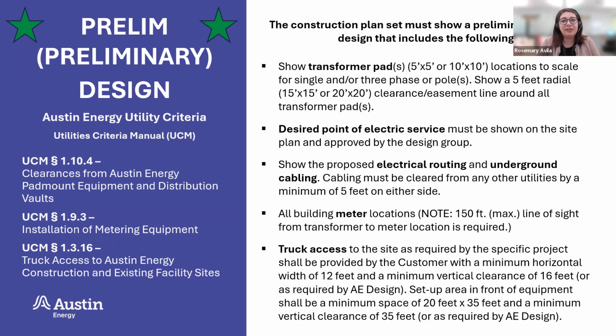You need to install a new pole. You need to connect to a different pole. So that's why we want it shown early on so we can start making those determinations. We want every proposed electrical routing underground shown. And again, that's to measure clearances, make sure you're not going under a pond or under a building or under a huge retaining wall or something like that. So we do need the routing shown and make sure that we maintain distances from that.